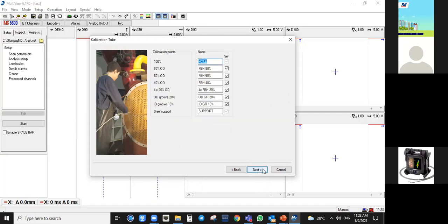So next, this one would be your calibration tube. Okay, so on your ASME calibration tube, you have these defects and support. So you have your flat bottom hole 80%, 60, 40, and then 20% flat bottom hole. Usually there are 4 as per standard. Okay. For your OD groove, you have 20, you have your ID groove of 10, and then you have the support plate. Okay. So as I mentioned a while ago, when you're using our calibration tube, you have 3 extra defects. So you will include that one later. You cannot put those defects here. You will need to include that one later on the setup. Okay.